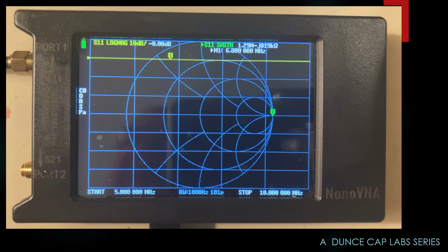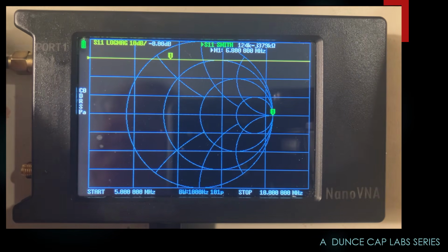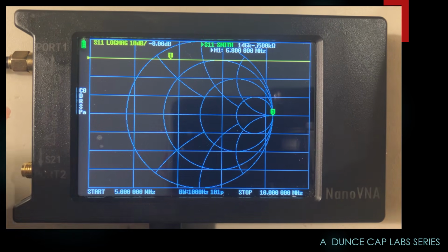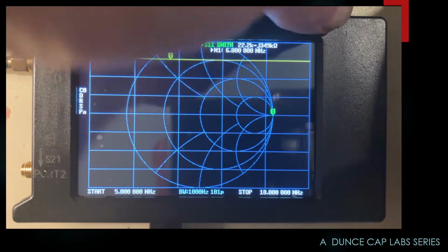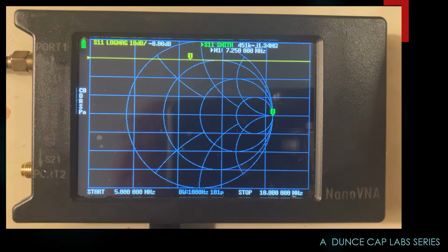So let's put an actual open on there, because like I said, I had nothing on the end. Let's put our real open on, which shields us from any electrical interference. And you know it's going to pass because it did without a shield. Okay, so we're calibrated across the spectrum for an open.